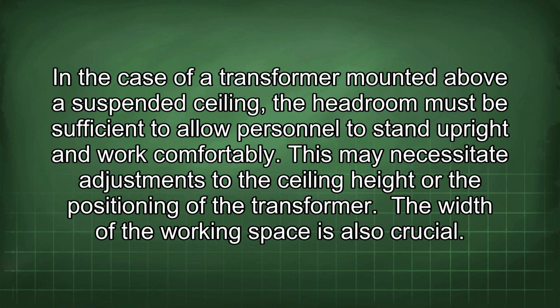In the case of a transformer mounted above a suspended ceiling, the headroom must be sufficient to allow personnel to stand upright and work comfortably. This may necessitate adjustments to the ceiling height or the positioning of the transformer. The width of the working space is also crucial.